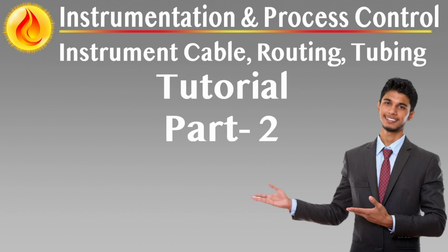However, all cables must be securely anchored with low-resistance clamps or cable fixings to prevent movement, reduce strain on terminals, and maintain EMC performance. Signal marshalling is centralized in main distribution frame, MDF, cabinets.